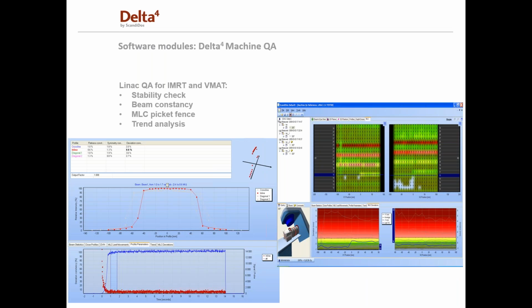In addition, we have a software module that's for machine QA. And this will check stability of the beam, beam constancy, MLC picket fence, and you'll be able to establish trend analysis. So this can help you with the analysis, with keeping track of what's going on with your machine.